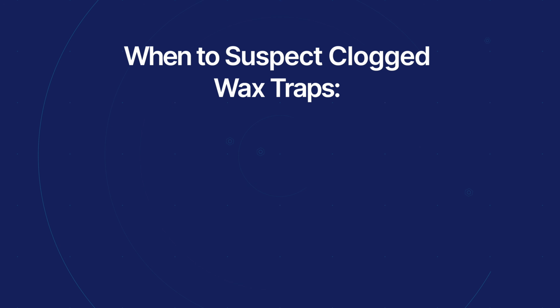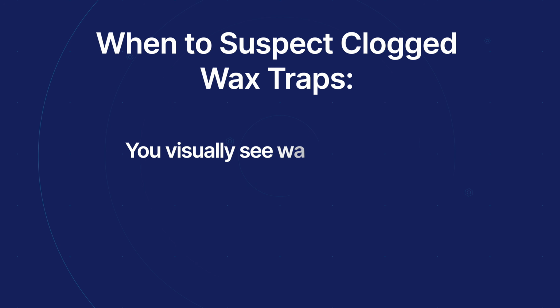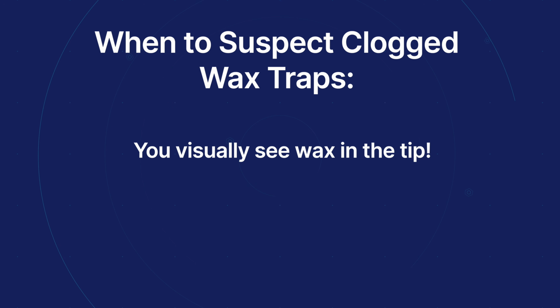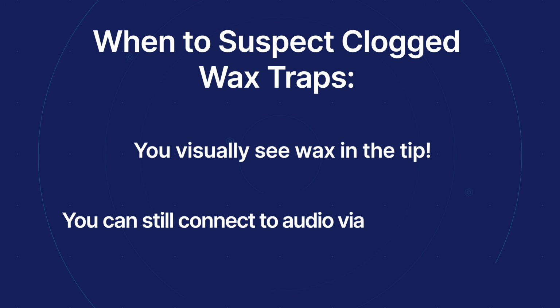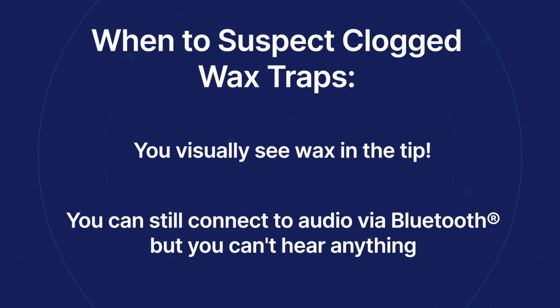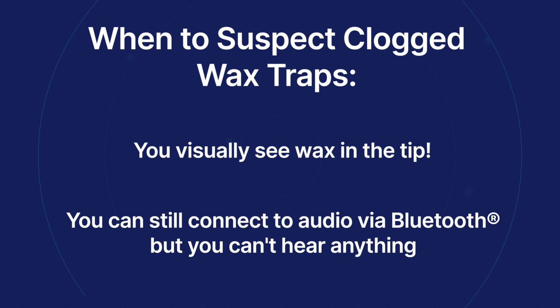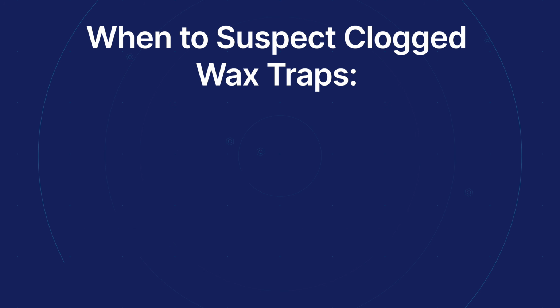A few things might give this away. First and foremost, if you look in the tip of your wax trap and you see a bunch of wax in there, chances are that's the problem. But also, if you turn on your hearing aid and you can see that it's connecting to your smartphone app and it says that it's on and it has a lot of battery and all of that, but you're not hearing any sound from it, chances are that wax trap is plugged as well.